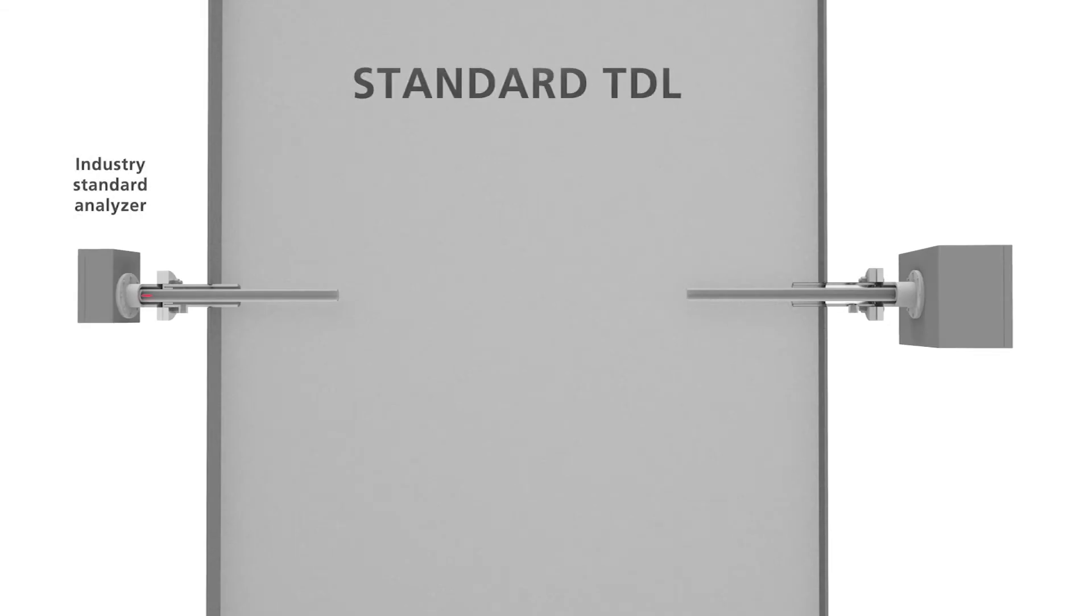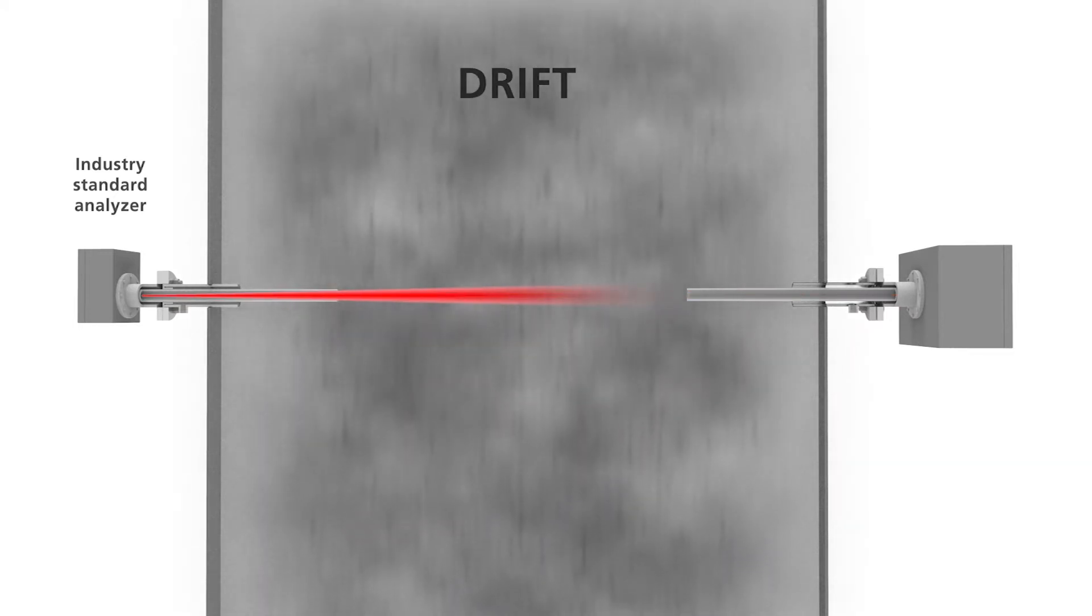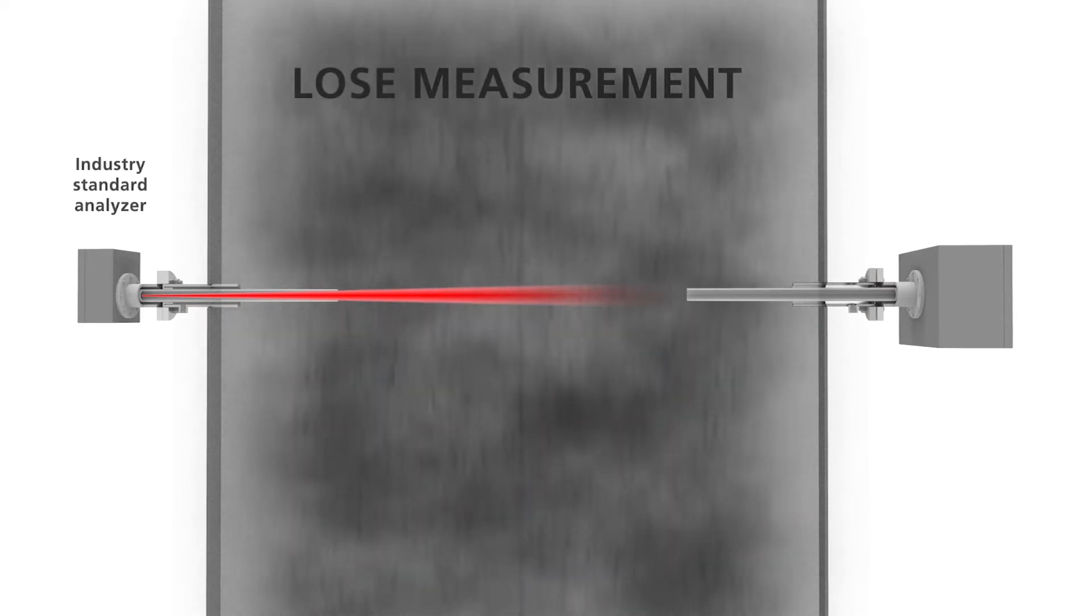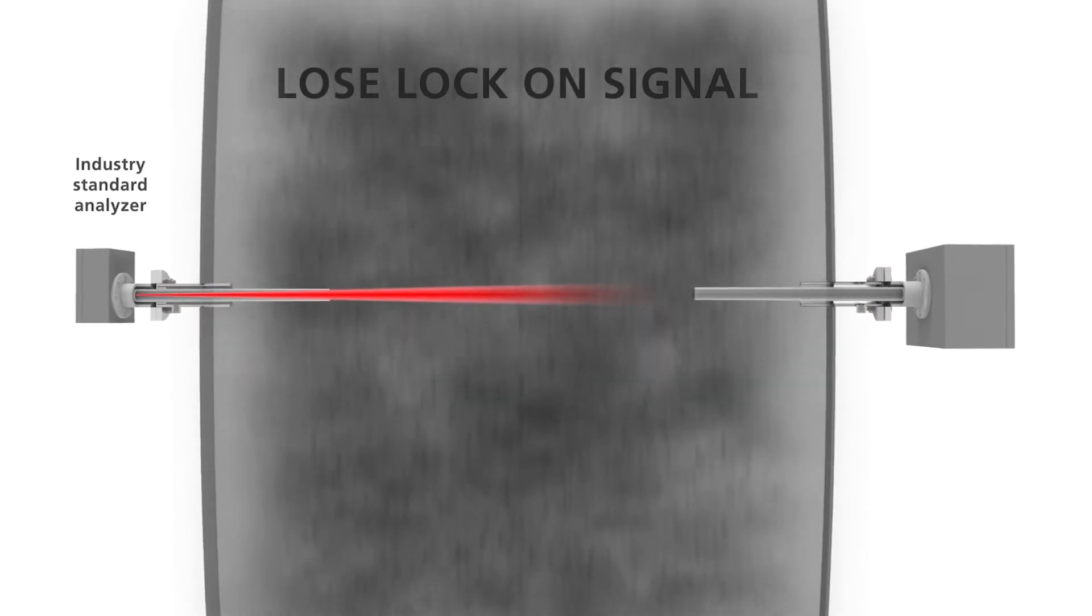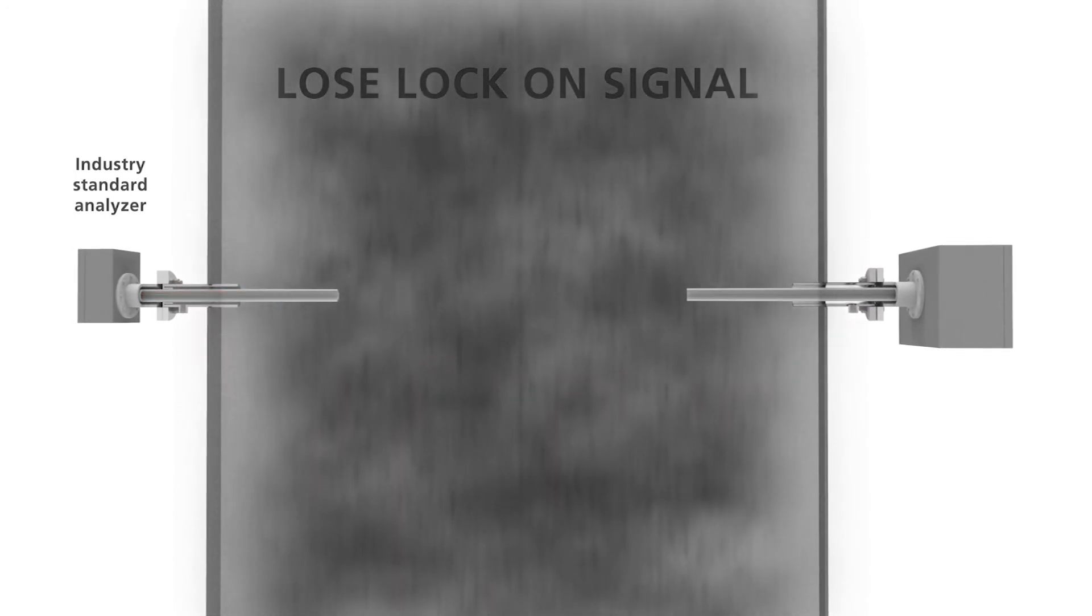As there is no physical interaction with the process, TDL offers a highly stable, fast and reliable measurement. Yet TDL analyzers can struggle in dust-heavy DeNOx environments with drift, and lose measurement due to mechanical movements, or lose lock on the process signal, returning incorrect measurements due to light scatter.